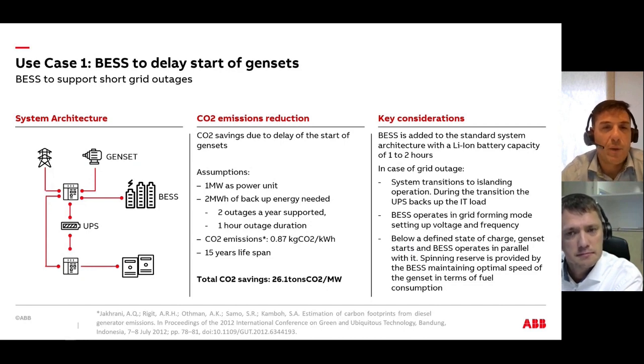The key consideration here is that the BESS, as I said, is added to the standard system with a lithium-ion battery capacity from 1 to 2 hours. So in case of a grid outage, the system is going to transition to island operation. And during that transition, the UPS is backing up the IT load. The BESS is then operating in grid forming mode and is setting up the voltage and frequency on that isolated grid.